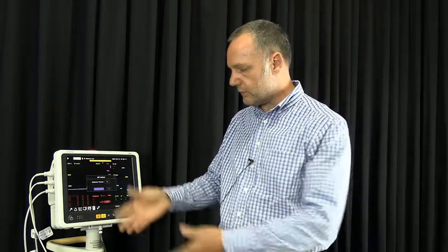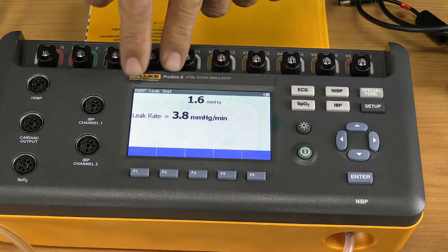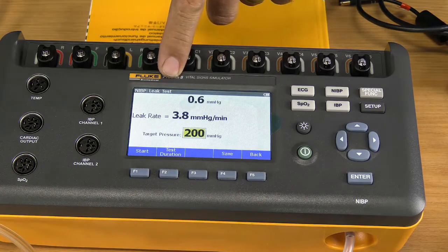In general, I think in the case of Philips, we allow a 6 millimeters of mercury drop over that 1 minute period. If it's more than that, then obviously our solenoids are not closing properly anymore, or the tubes have expanded too much. We need to replace some tubes. Looking at our cuffs, our pipes, everything down the line, we've got to inspect that. And let's see, we're almost there. And there you can see now, I've picked up a leak rate of 3.8 millimeters of mercury over a 1 minute period, which is totally fine.